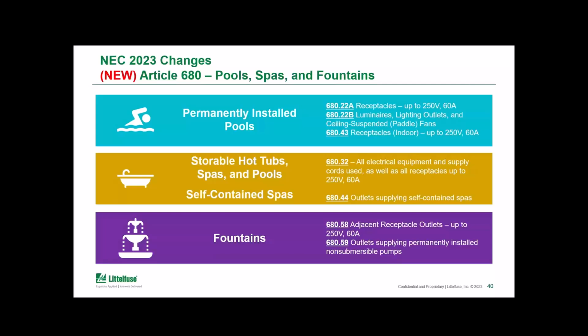So in 2023, the code was updated to essentially say that in all areas where Class A GFCIs have been required in the past, if in those applications there is equipment or service installed above 150 volts to ground up to a maximum of 480 volts phase to phase, it now must incorporate a special purpose GFCI. And this does cover both receptacles, which would be the terminology for plug and cord connections, as well as outlets, which would be a hardwire connection.